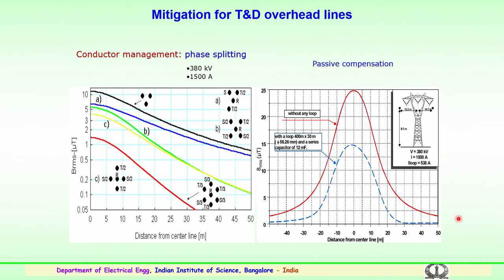Further in conductor management, there is one more option, which is phase splitting. A typical example is shown here for a 380 kV transmission line carrying a current of 1500 amps, and you can see for various configurations A, B and C how the magnetic field performance varies with distance from the center. You can see how the configuration is given here, so that this will improve the performance and give better information to the utility engineers, who could plan how properly the conductor management could be made for reducing the magnetic fields or the electric fields particularly.